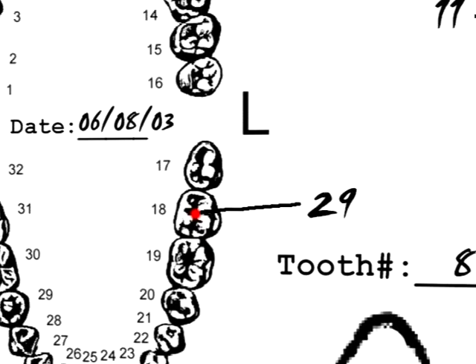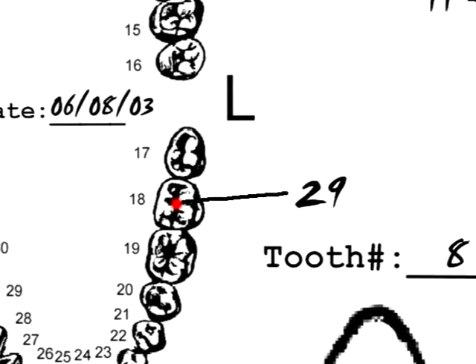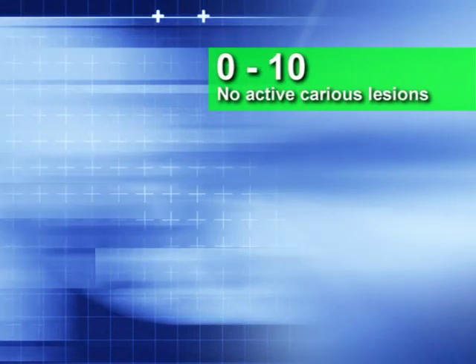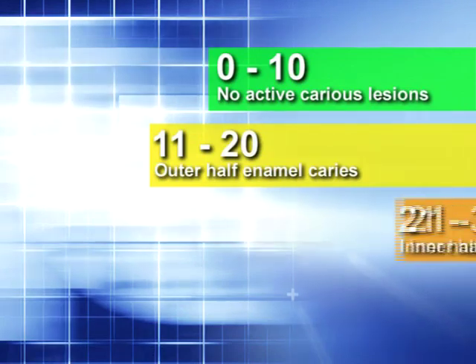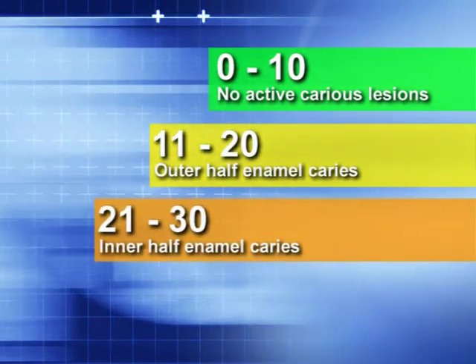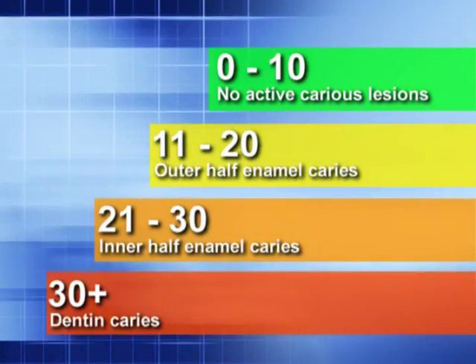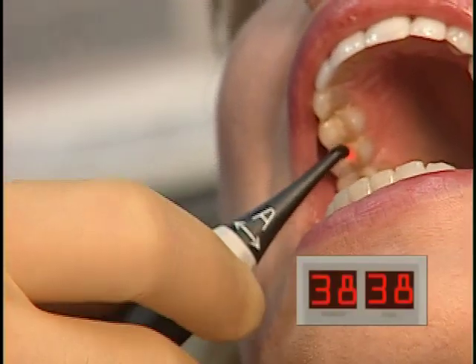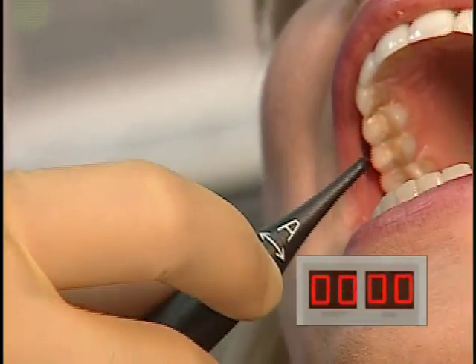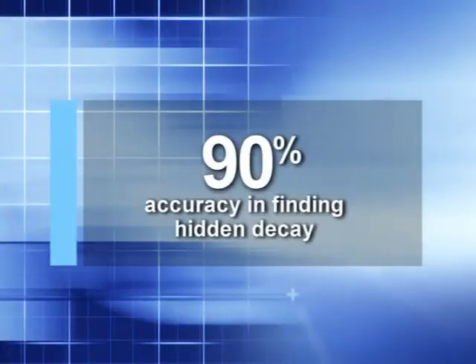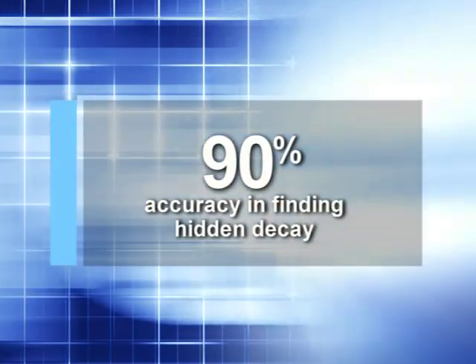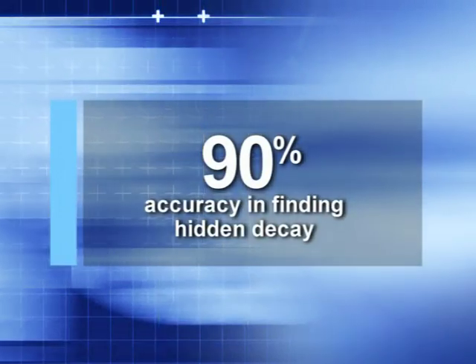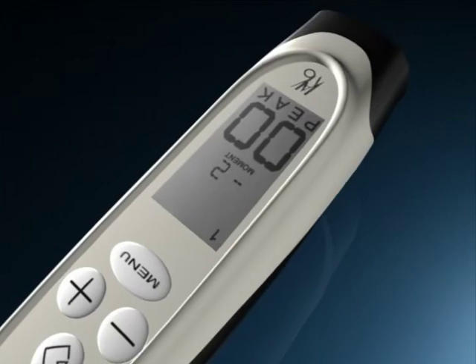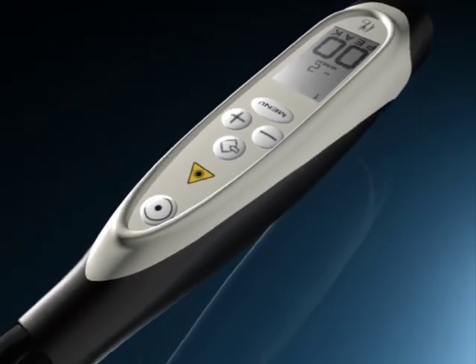Research indicates the following correlation to caries: 0 to 10, no active carious lesions; 11 to 20, outer half enamel caries; 21 to 30, inner half enamel caries; 30 and above, dentin caries. Peak readings are reset to 0 with a simple squeeze of the rubber ring on the handpiece to prepare for examination of the next area. Clinical research studies show these findings to be accurate in detecting over 90% of all hidden decay. However, some decay may be too small or too deep for even the DIAGNodent to detect.